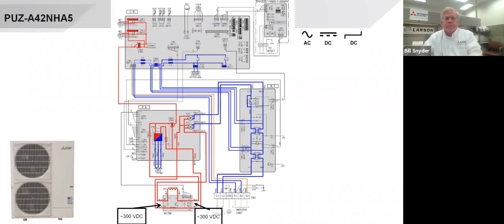Also up at the top here, these are thermistors labeled TH, temperature thermistor. TH, there's a 3, a 6, a 7, and a 32. This is the outdoor unit. So we have the entering coil thermistor in the outdoor unit, the leaving coil thermistor, the thermistor that's measuring outdoor ambient temperature, and the one that's the discharge temperature on the compressor there.